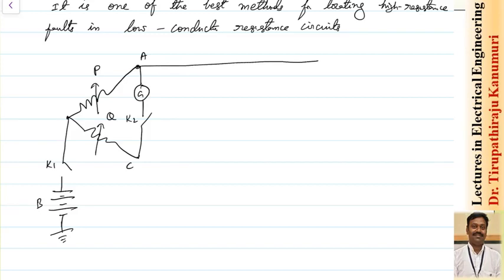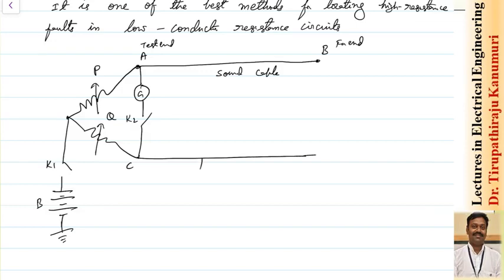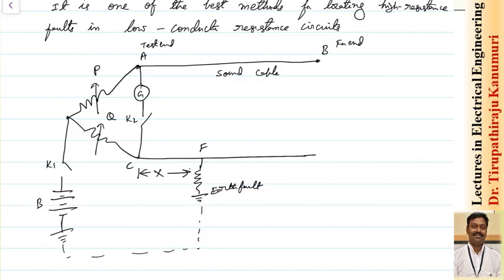There should be a healthy conductor — the sound cable, meaning a cable without any type of fault. This is the far end of the cable, and this is the test end of the cable. Now there is a faulty cable, and let us assume this faulty cable has a fault at location F with some fault resistance. This is the earth fault — the fault is connected to earth. We are first discussing how to diagnose the earth fault. Let us assume this earth fault happened at a distance x from this end, and I am connecting the far ends using a small conductor having zero resistance.